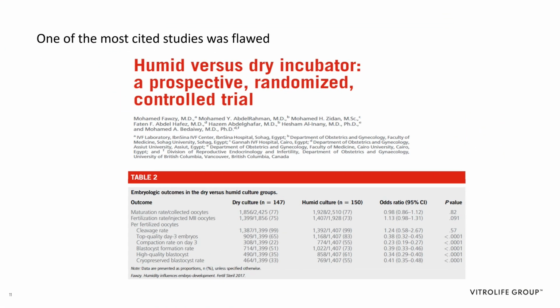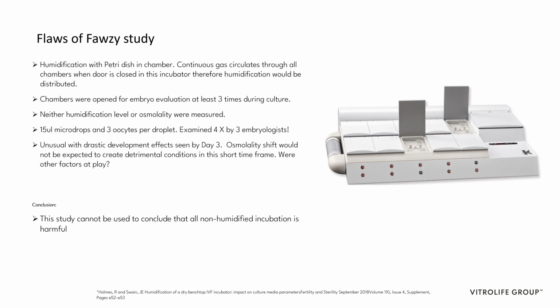This is one of the most cited studies we see about humid versus dry, and there are very, very many flaws with this. First of all, the type of incubator: they claim they achieved humidity by putting a water dish in the chambers that were humid. This is also a system with premix. But in fact, they never measured the humidity, they didn't measure the osmolality, and the fact is, this type of incubator, when you close that chamber, it recirculates the air.